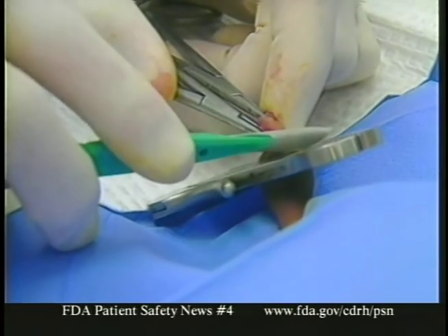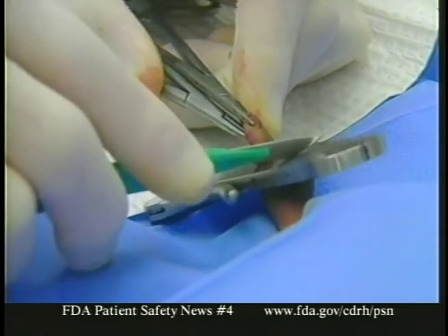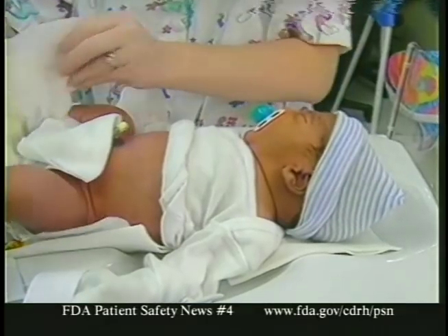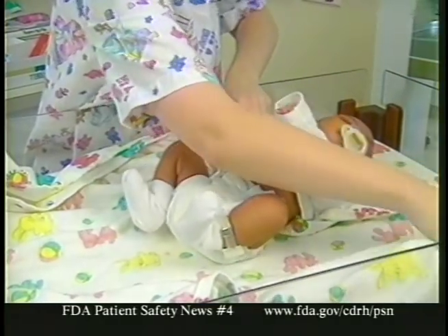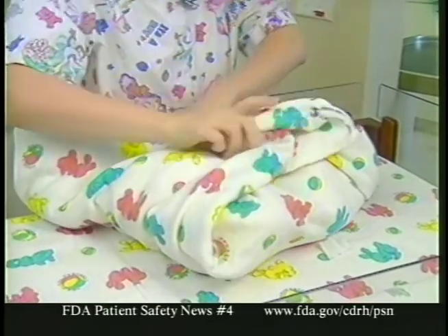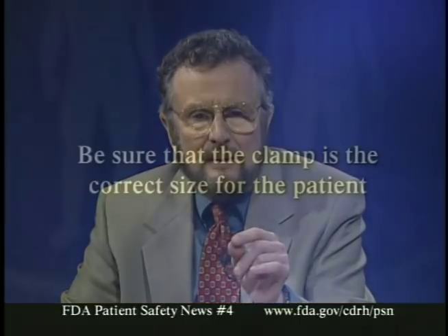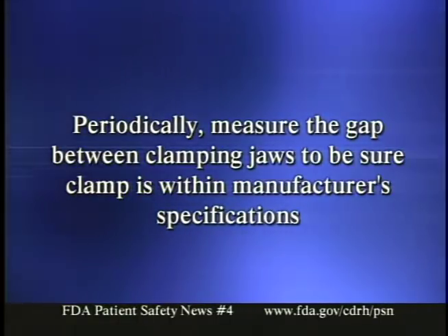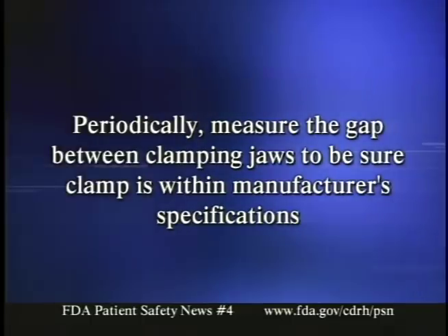With Mogen type clamps, problems arise when the jaws of the clamp are too large for the patient. This can allow too much tissue to be drawn through the opening, so an excessive amount of foreskin or even a portion of the glans penis is removed — either because the clamp is not within the manufacturer's specifications, or because the wrong size clamp is selected for the patient. Note that some manufacturers have two sizes: one for infants and one for adults. To prevent problems: first, be sure the clamp is the correct size for the patient; and second, periodically measure the gap between the clamping jaws to be sure it's within the manufacturer's specifications.